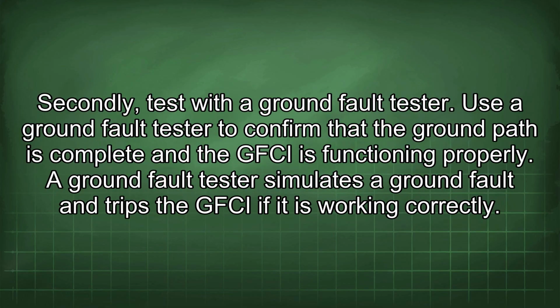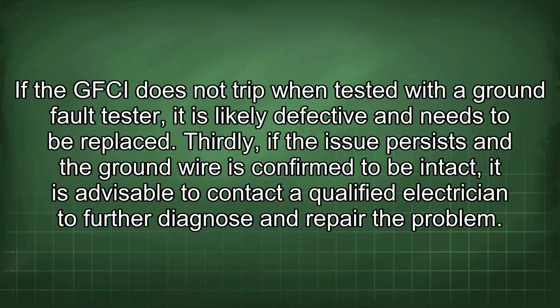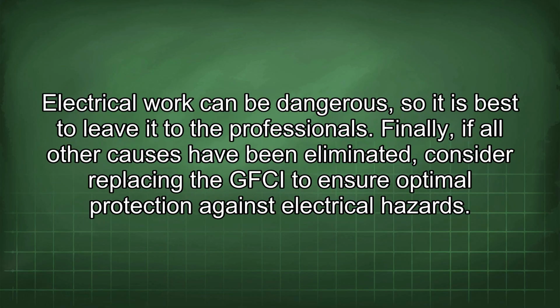Secondly, test with a ground fault tester. Use a ground fault tester to confirm that the ground path is complete and the GFCI is functioning properly. The ground fault tester simulates a ground fault and trips the GFCI if it is working correctly. If the GFCI does not trip when tested with the ground fault tester, it is likely defective and needs to be replaced. Thirdly, if the issue persists and the ground wire is confirmed to be intact, it is advisable to contact a qualified electrician to further diagnose and repair the problem. Electrical work can be dangerous, so it is best to leave it to the professionals.